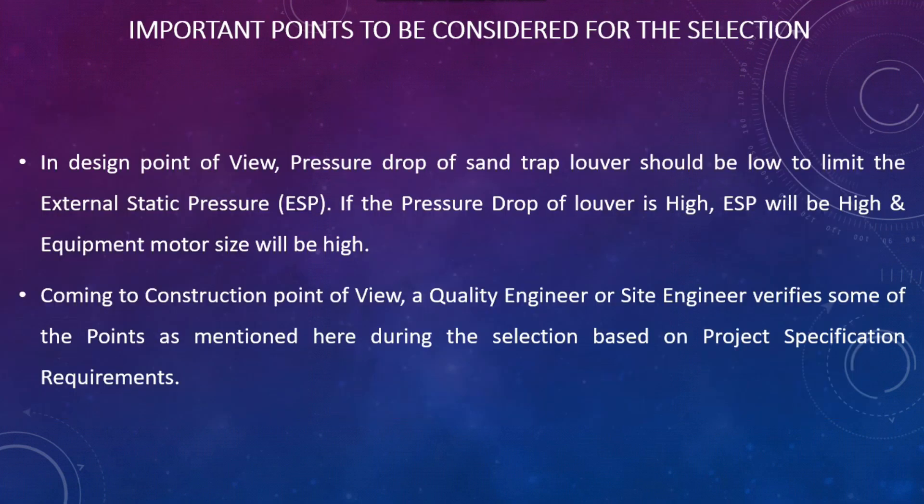From a design point of view, the pressure drop of a sand trap louver should be low to limit the external static pressure, or ESP. If the pressure drop of the louver is high, the ESP will be high and also the equipment motor size will go high.